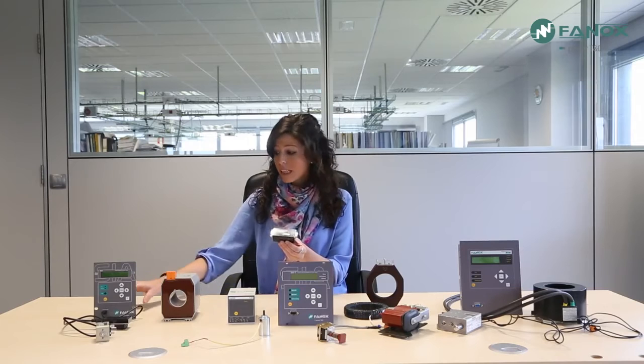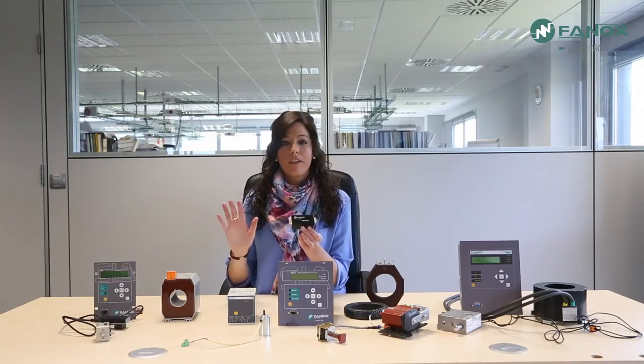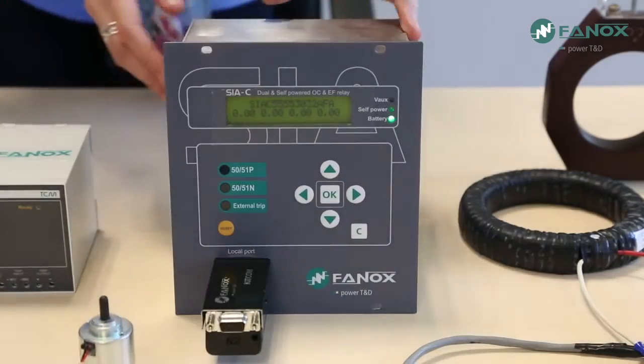How can the correct installation of the self-powered relay be checked? Without auxiliary power, it might seem the only way to verify is once the relay is installed — however, this could be dangerous, because if something is incorrect in the relay, the transformation center would not be protected. To solve this, FANOX offers the KITCOM — an external battery working with two AA-type batteries, connected to the front port of the relay. Since relays can have a DB9 port or USB port, there is a KITCOM for each situation. Once connected and switched on, together with a test menu, it lets us check not only the hardware of the relay but also the outputs and the trip circuit, verifying everything is correct before the transformation center is powered up.